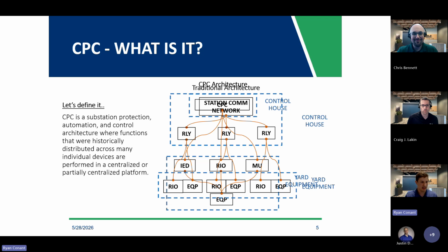it's a wordy one, but we could say that it's a substation protection, automation, and control architecture where functions that were historically distributed across many individual devices are performed in a centralized or partially centralized platform. CPC will eliminate a lot of the relays and devices, in both a traditional or 61850 design, making the system much more streamlined and standardized than a current traditional design. This isn't to say that CPC cannot contain any hardwired or traditional electrical circuits, but the main benefit of CPC will be realized by migrating to more of a communication-based scheme that could utilize either IEC 61850 or a vendor proprietary communications protocol. Contrary to popular misunderstanding, CPC is not just one big relay, and it's not simply 61850. It's really an architecture shift that's moving towards a centralized computing platform.